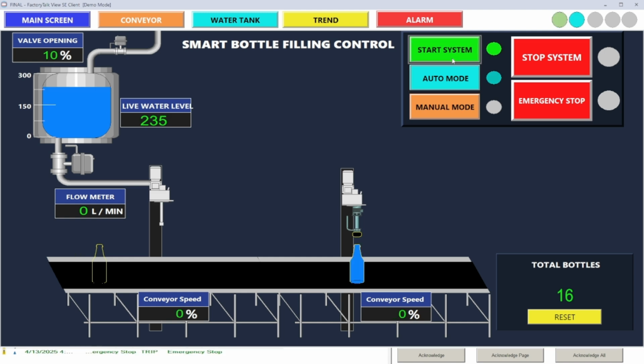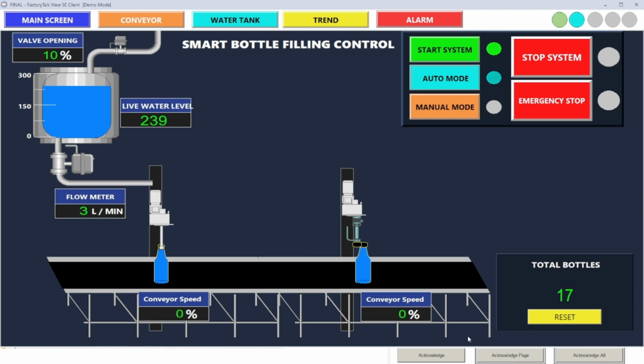Back on the HMI, there's a real-time bottle counter on the main screen. I've labeled it clearly so the operator knows how many bottles have been processed. The system also features a system status indicator that blinks when the system is running and stops when it's halted. These little UI elements help bring the SCADA to life.